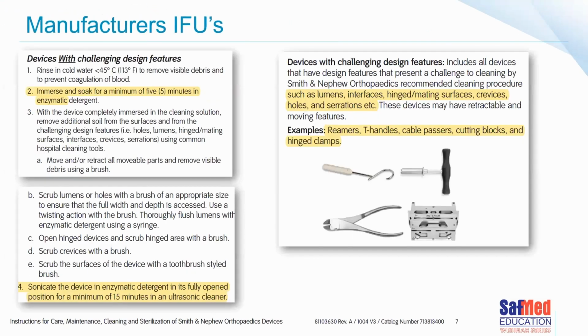This is another set of instructions for use that's more specific to orthopedic instruments. And please, when buying new instruments or devices for an operating room or for a hospital or a doctor's room, doesn't matter what the setting is, please always ask for the instructions for use first. Needless to say, to be able to check that you have the equipment that's needed to correctly reprocess those devices. You can see in this example from the manufacturer's instructions for use, it states that devices defined as challenging designs, like reamers or T-handles and cutting blocks and hinge clamps, for example, in this IFU, they need to be cleaned in an ultrasonic cleaner.